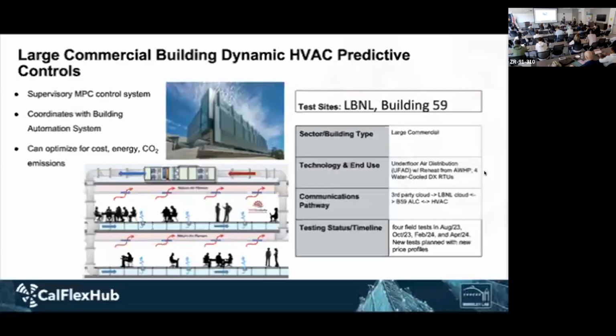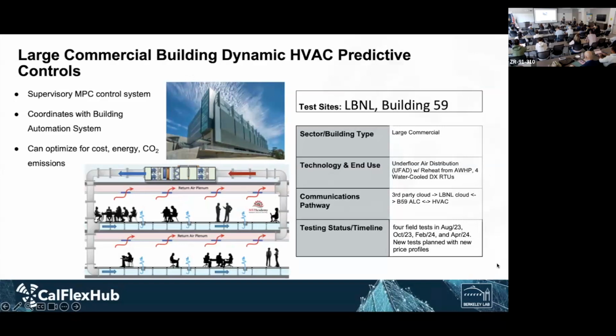To give an idea of how that works, you can take a look at the figure on the left, where we have 4 rooftop units that basically supply air to the concrete base of the floor, and then the air seeps through the building and goes back into the rooftop units. The rooftop units provide ventilation and cooling for the building, and the MPC can control the supply fan speed of each of the rooftop units and the supply air temperature set point.